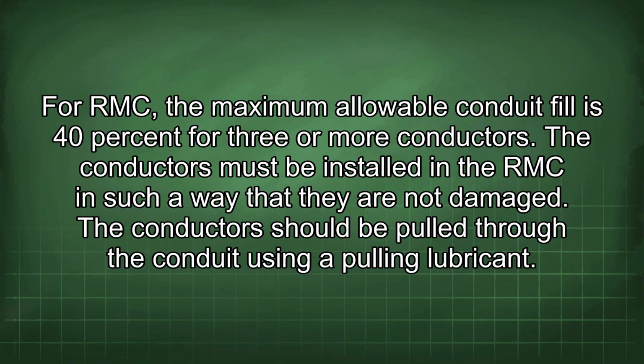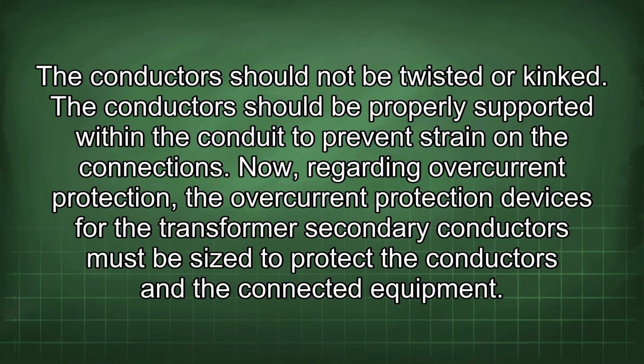The conductors must be installed in the RMC in such a way that they are not damaged. The conductors should be pulled through the conduit using a pulling lubricant. The conductors should not be twisted or kinked. The conductors should be properly supported within the conduit to prevent strain on the connection.